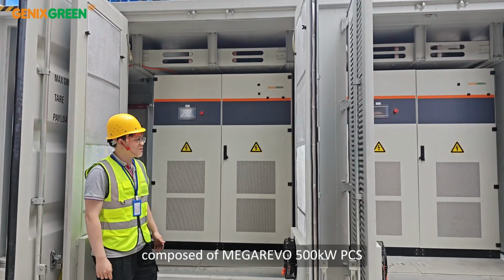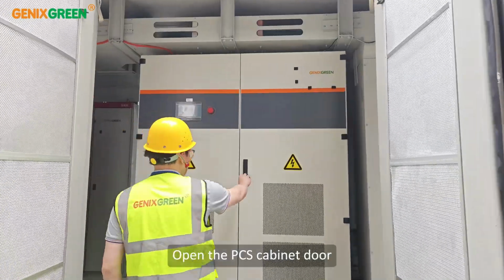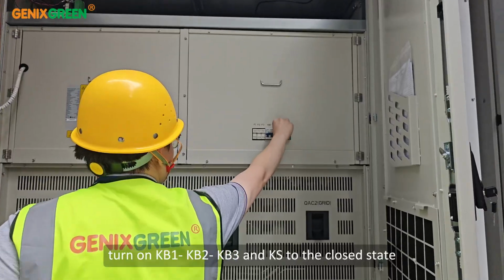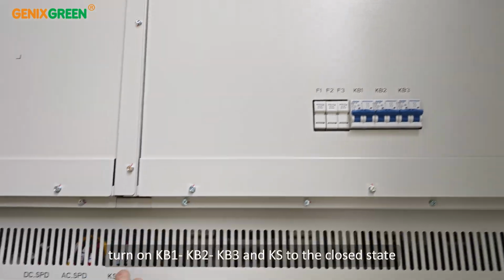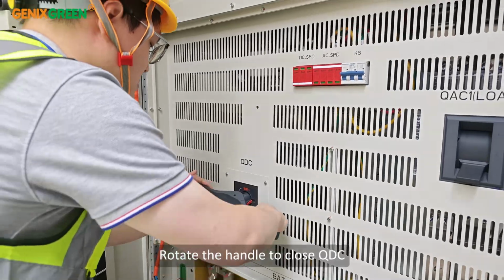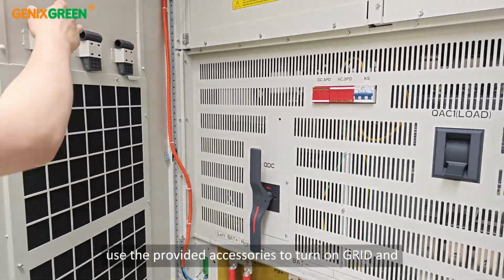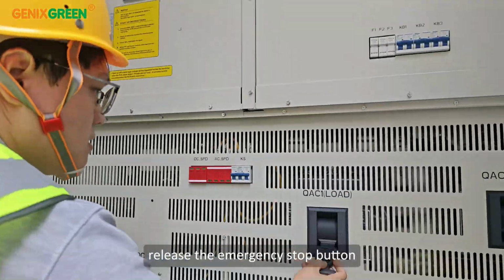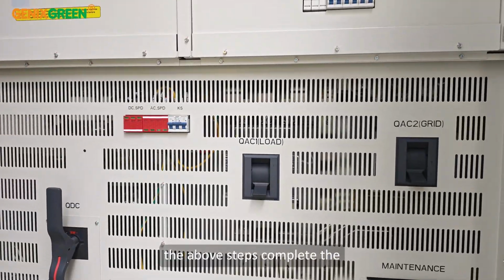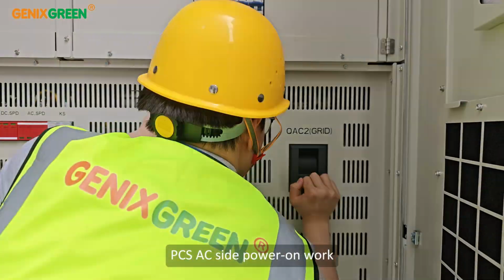The AC side of the container is composed of megawatt-level 500 kilowatts PCS. Open the PCS cabinet door, turn on KB1, KB2, KB3 and KS to the closed state, rotate the handle to close QDC, use the provided accessories to turn on grid and release the emergency stop button. The above steps complete the PCS AC side power on work.